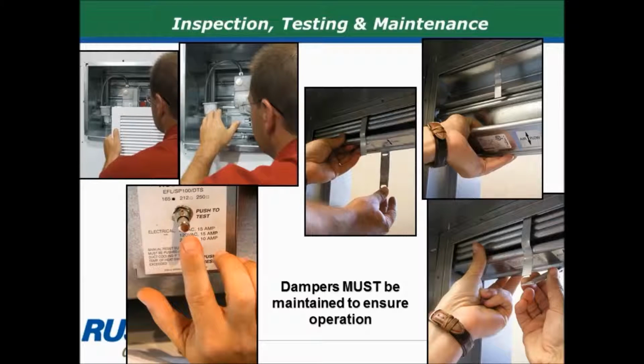Inspecting, testing, and maintaining dampers is really crucial. After all, these are life safety products. These are designed to help save lives in the event of a fire. The problem is, dampers are installed way up and out of the way, out of sight, out of mind, and unfortunately, they're not tested nearly as often as they ought to be. We can see here some of these photographs. On the left-hand side, there's a test switch where this is a motor-driven damper. You press the switch, it cuts the power, and then you see whether or not the blades close properly.